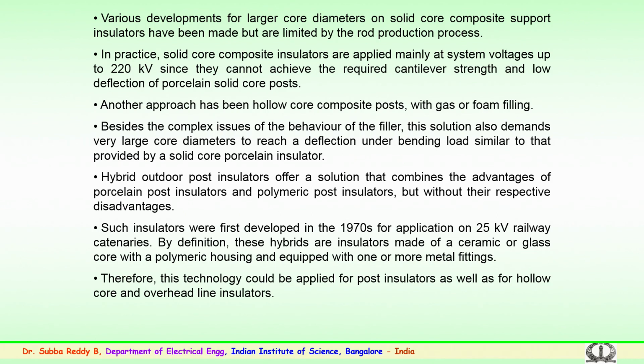In practice, solid core composite insulators are mainly applied for system voltages up to 220 kilovolts, since they cannot achieve the required cantilever strength. Mechanical strength plays a role, as does the low deflection of a porcelain solid core post. That is why solid core composite insulators were mainly used up to 220 kilovolts.